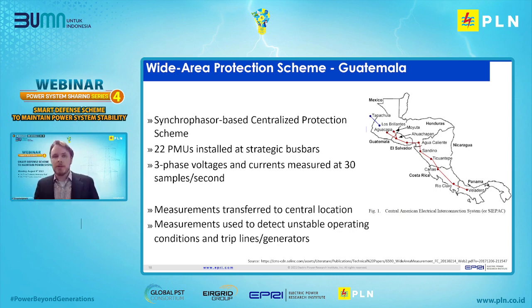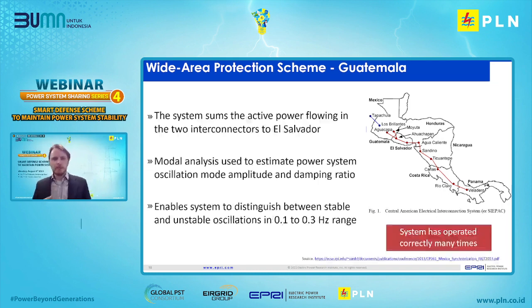So this is a very modern example of wide area protection, but this required a lot of design of very highly resilient communications systems, as well as the new PMUs and the central system for determining the tripping decisions as well. So just moving to the next slide. In this particular case, the system looks at the active power flowing across 2 interconnectors between El Salvador and Guatemala. It uses modal analysis then to estimate the power system oscillation mode amplitude and damping ratio.